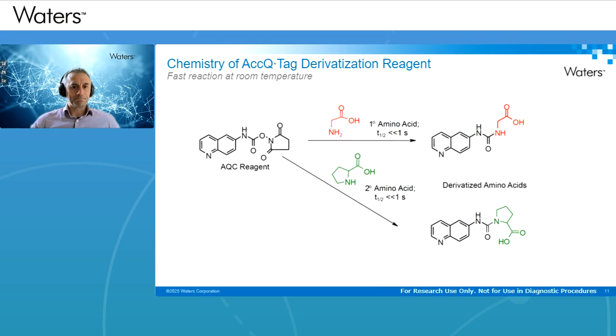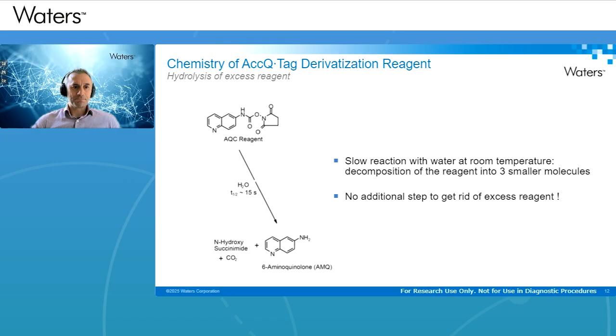So on the previous slide, you saw the reaction that occurs upon mixing of the sample, the buffer, and the reagent. It is, however, important to make you aware that a second, albeit slower, reaction takes place in parallel to the derivatization. In fact, water will attack the AccQ-Tag reagent to form 6-aminoquinoline, we call it AMQ, N-hydroxysuccinimide, and CO2. This means that any excess of reagent that you will evidently have will be quickly destroyed by the presence of water. That also means that there is no need for a liquid-liquid extraction or anything else to get rid of the excess of reagent.